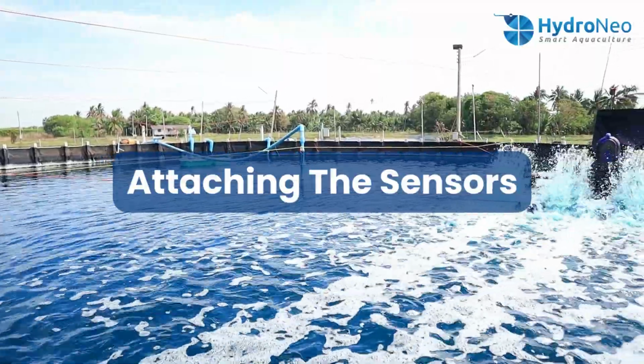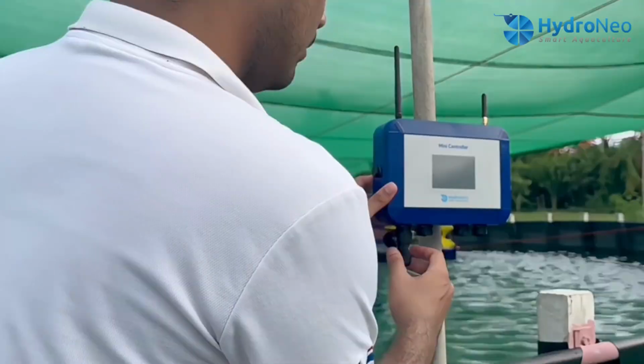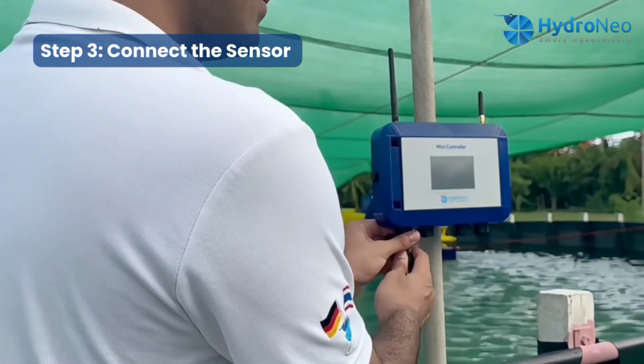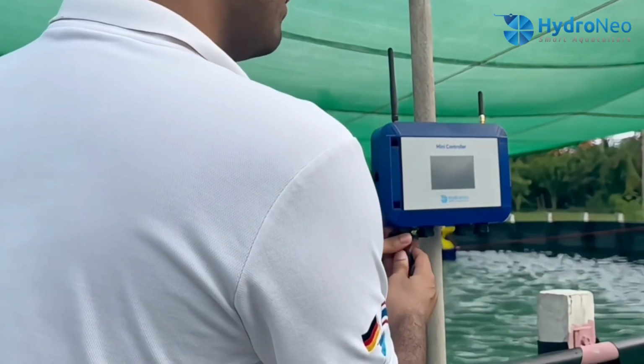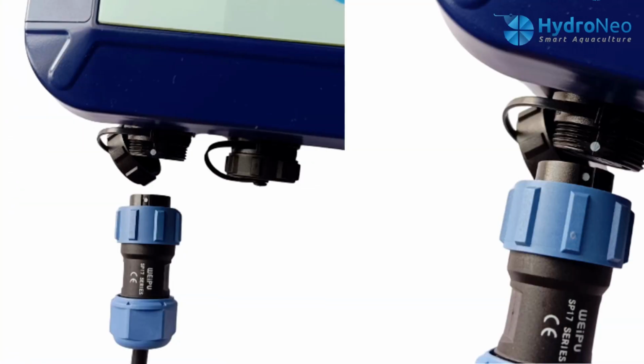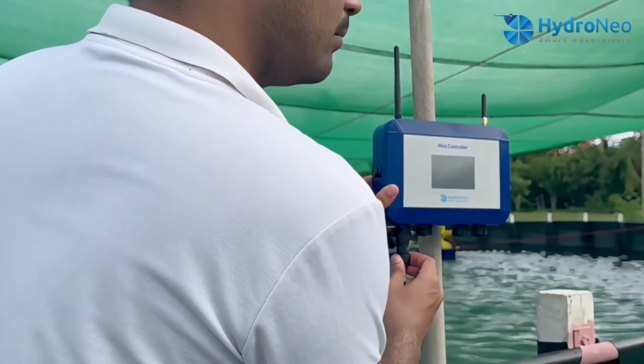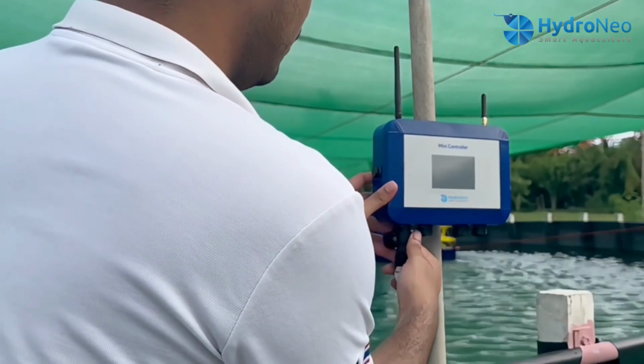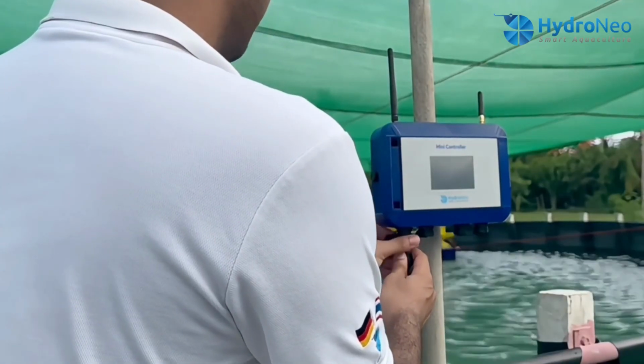Attaching the sensors. Step 3. Connect the sensor. Take your dissolved oxygen sensor cable and align the white dots on the plug and the port. Gently push the plug into the port until it is seated. Then, tighten the locking ring securely. This ensures a waterproof seal.